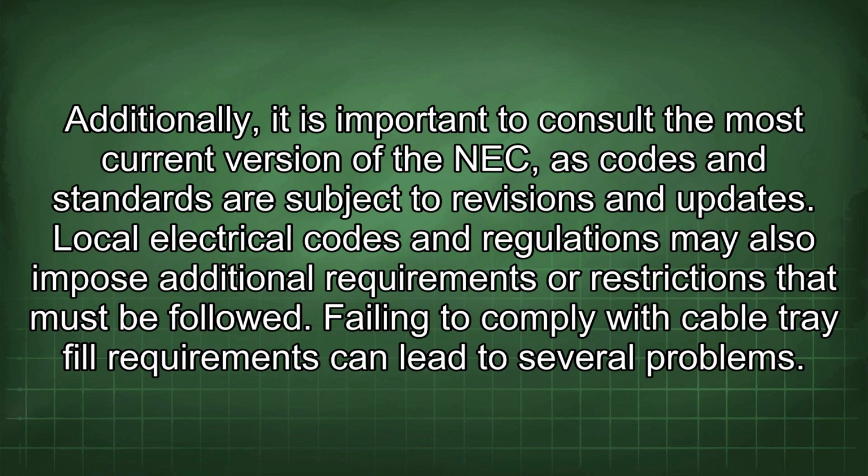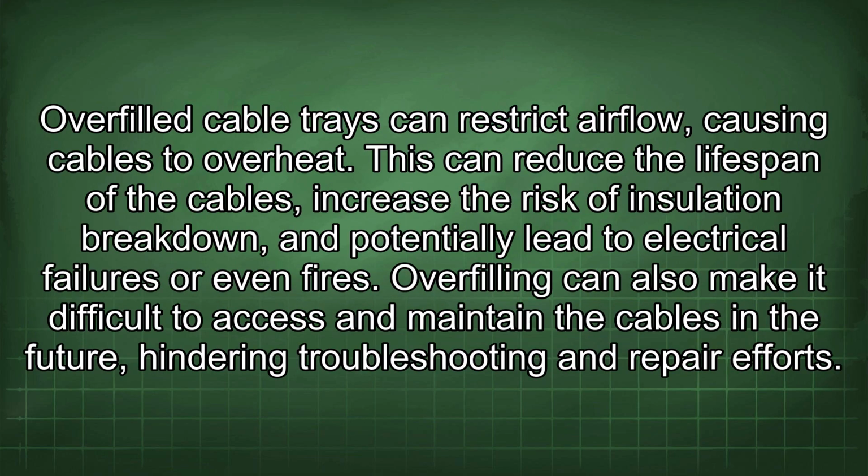Failing to comply with cable tray fill requirements can lead to several problems. Overfilled cable trays can restrict airflow, causing cables to overheat. This can reduce the lifespan of the cables, increase the risk of insulation breakdown, and potentially lead to electrical failures or even fires. Overfilling can also make it difficult to access and maintain the cables in the future, hindering troubleshooting and repair efforts.